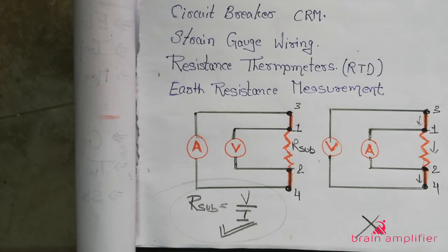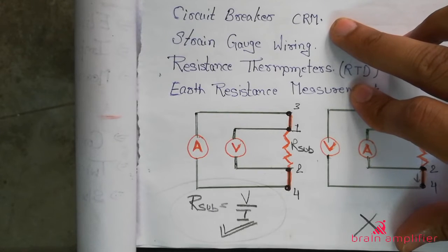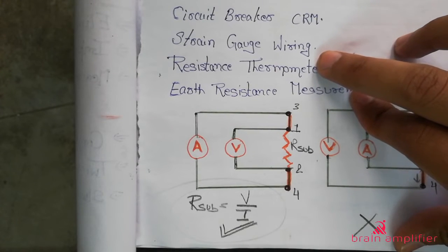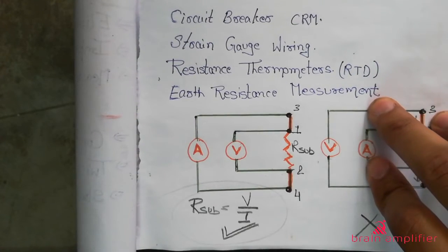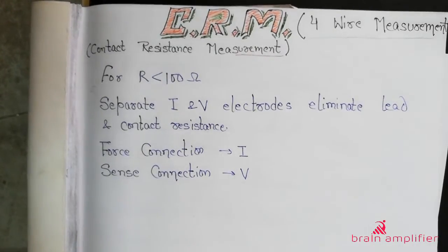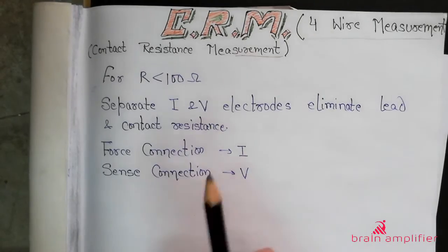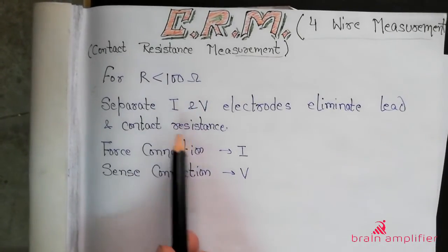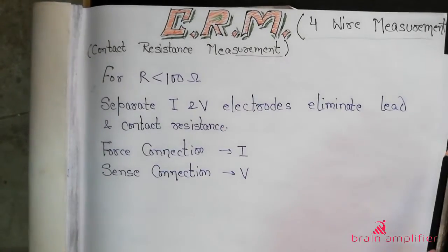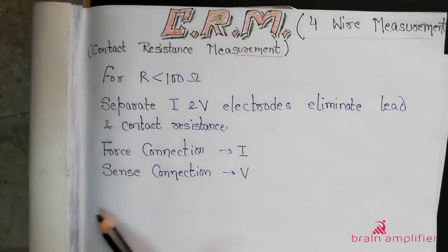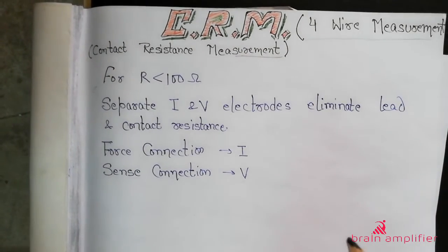The applications of four-wire measurement include circuit breaker contact resistance measurement, because those contact resistances are in the range of a few micro-ohms. It is also used in earth resistance measurement. In general, we use this technique when our resistance is less than 100 ohms. In this method we have separate current leads and voltage leads — current leads are called force connections and voltage leads are called sense connections.